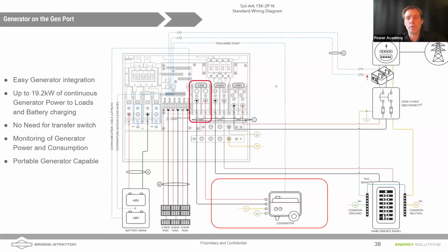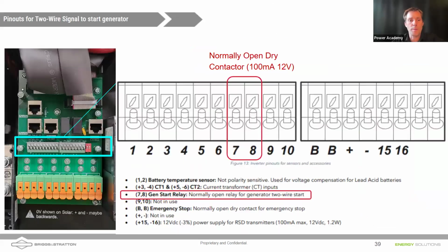If we are putting the generator on the gen port for a grid-tied system, so you've got utility coming through the grid port, you've got a generator coming in through the gen port, you're going to be limited to 19.2 kilowatts of continuous generator power. It's okay to put a bigger generator on this port, but you do want to have a breaker sized at 80 amps of continuous power. Right, so you'll want to downsize that breaker if you're putting a bigger generator on there to make sure you're not pulling more than 80 amps of continuous power. You can also do the settings in the Sol-Ark to limit how much overall power you're pulling through the gen port. So we'll talk about that.